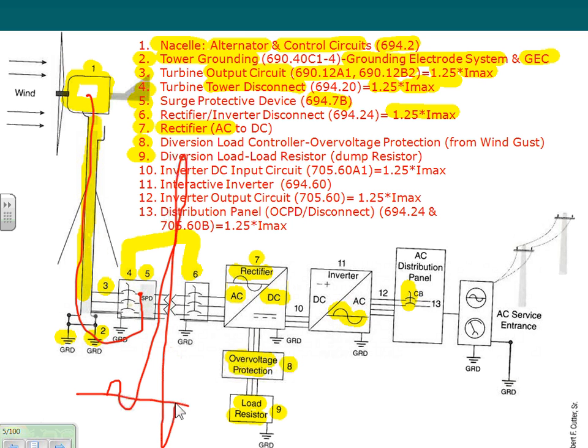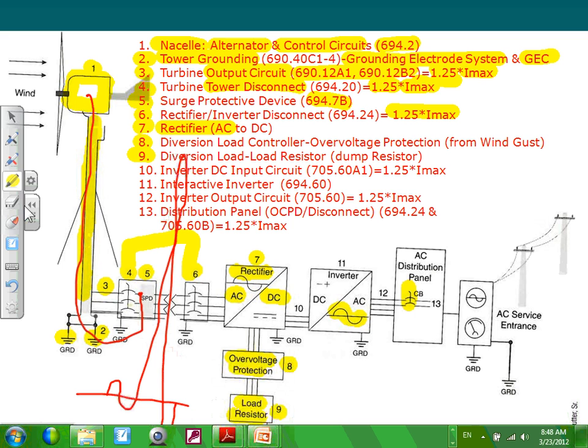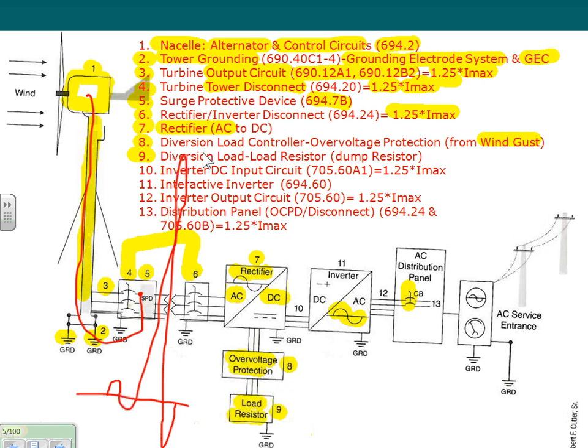You have a storm at 65 miles an hour. Those guys don't run. They have mechanical and or electrical braking. They completely stop them. Otherwise, they can't control them in a big storm. So that's your control system to control the voltage. We need to be able to control the voltage within a limit that we can invert it. Otherwise, we burn the inverter if the voltage is so high. That's mostly done by manufacturers. And again, wind gust, control the wind gust.